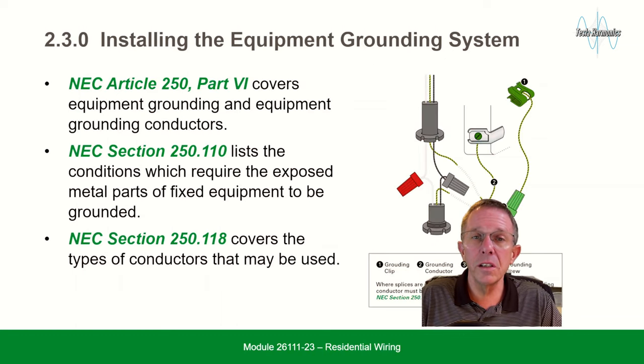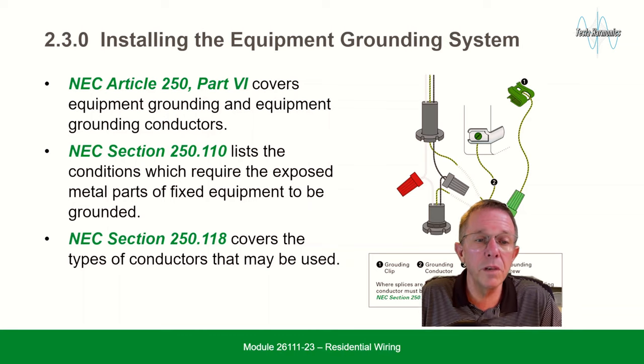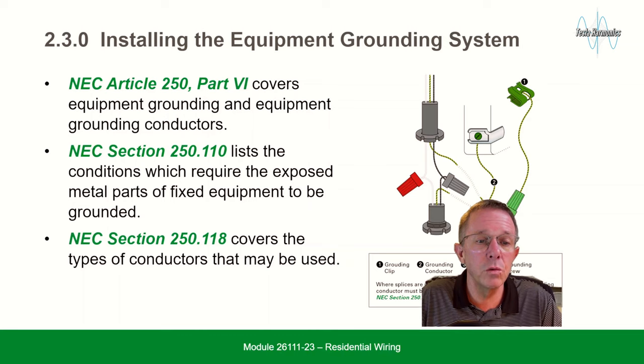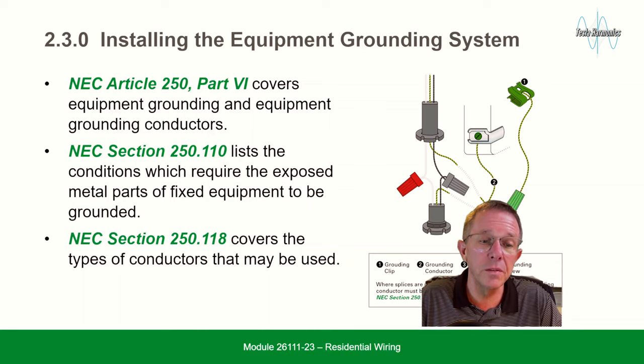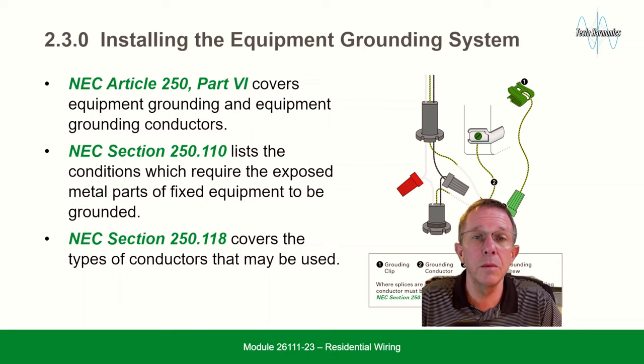Installing the equipment grounding system: NEC article 250 covers equipment grounding and equipment grounding conductors. NEC section 250.110 lists the conditions which require the exposed metal parts of fixed equipment to be grounded. NEC section 250.118 covers the types of conductors that may be used.